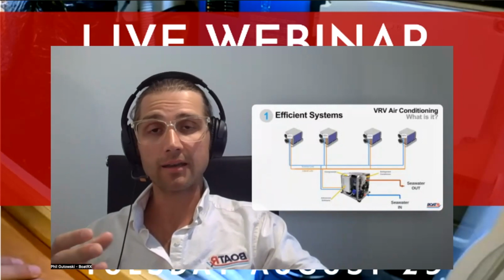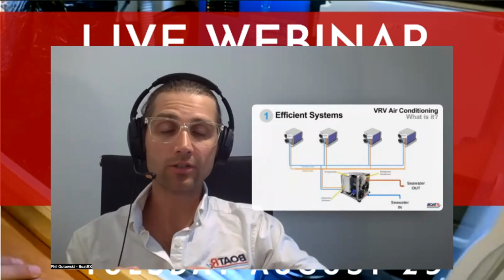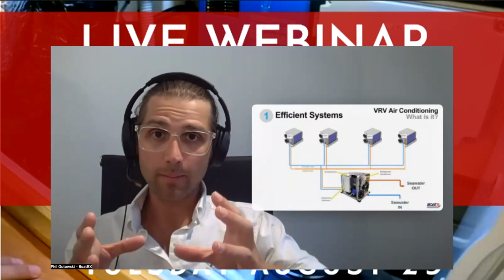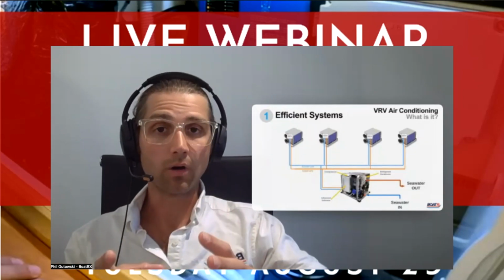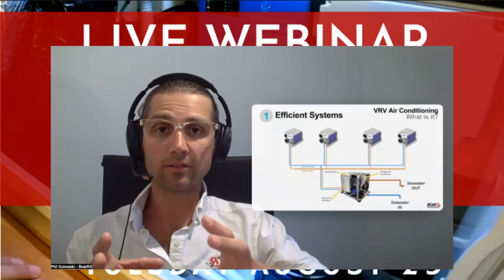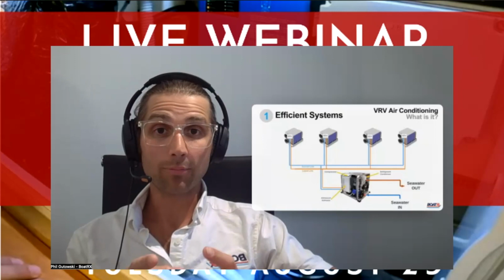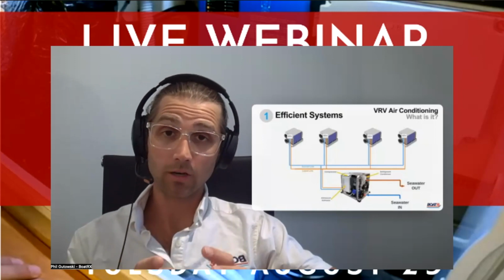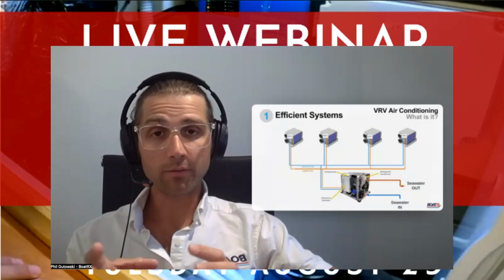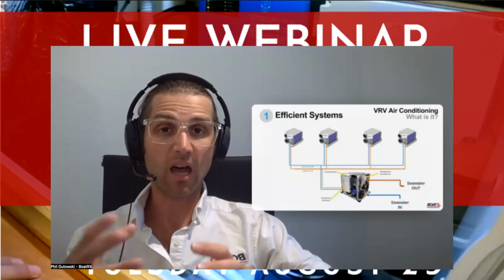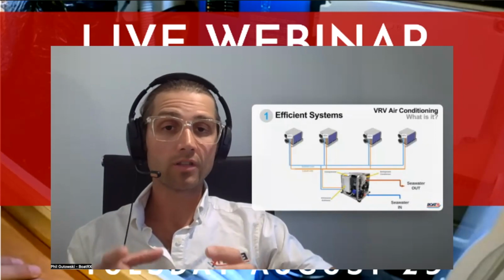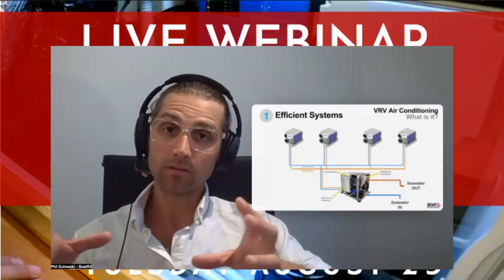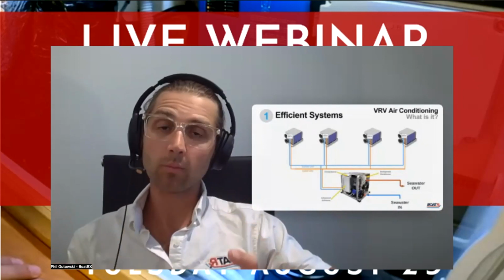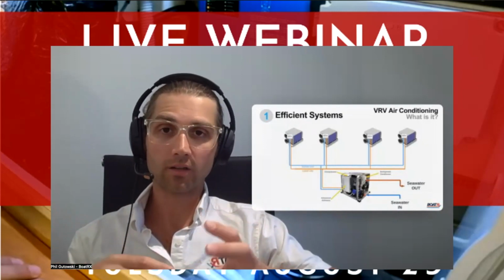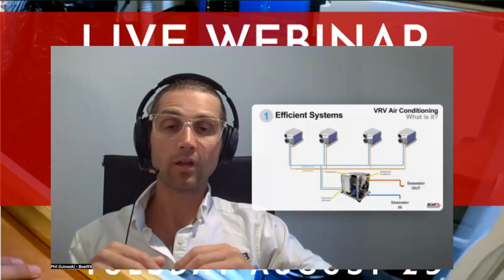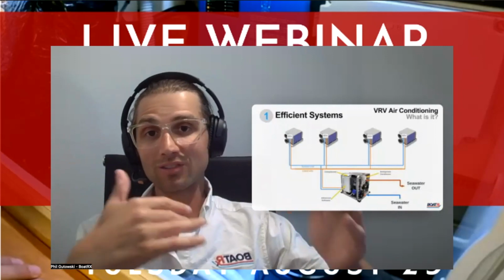The other thing to point out is that because it adapts so well to these different environmental changes, if you have a system that's operating in New England in 70 degrees seawater, and then you take that same system down to Fort Lauderdale, and it's operating in close to 100 degrees seawater, like we saw this year, the old style systems that have been around forever don't do anything different. They just operate more inefficiently when they get into warmer water. Whereas a VRV system is constantly adapting to these different changes. And if it encounters warmer water, it's going to run the compressor faster, and it's going to create a higher head pressure of the refrigerant to maintain the temperature differential between the seawater and the hot refrigerant.